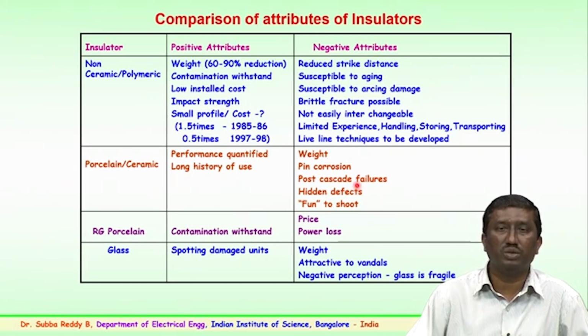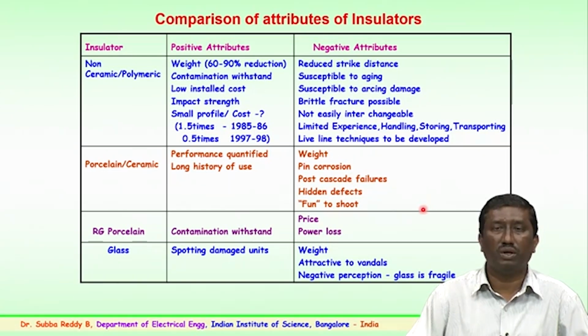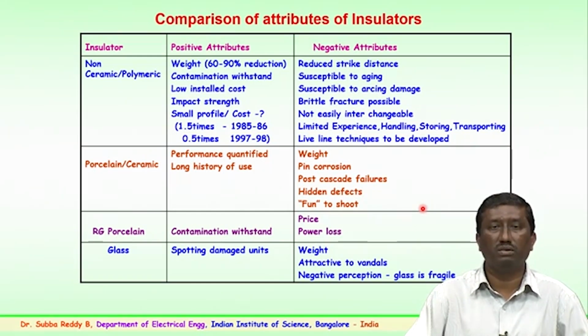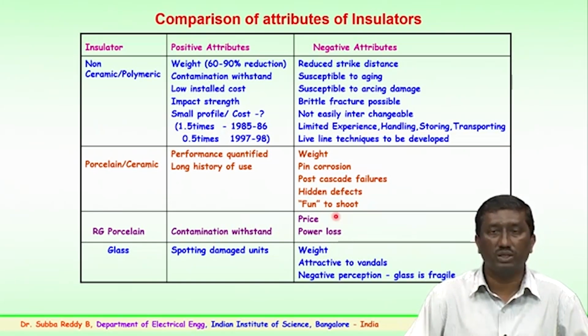But yes, negative attributes are that the weight of the string goes on increasing with the voltage level, pin corrosion has been observed, sometimes cascade failures have happened, and hidden defects in the material could lead to a problem. And RG porcelain, a resistive glaze porcelain, is the newer version of the porcelain insulators, coated with the resistive glaze to improve the voltage distribution on the surface of the insulator and also for better contamination withstand. But again here the price or cost of the insulator goes up, and sometimes it has been noticed that power loss happens because of losing its properties over a period of time.